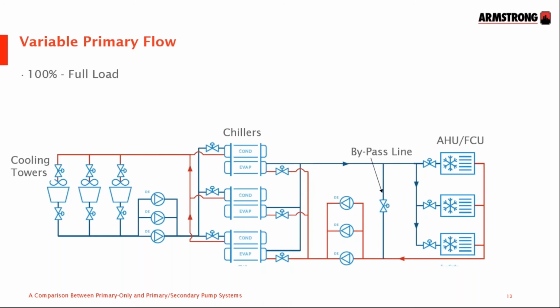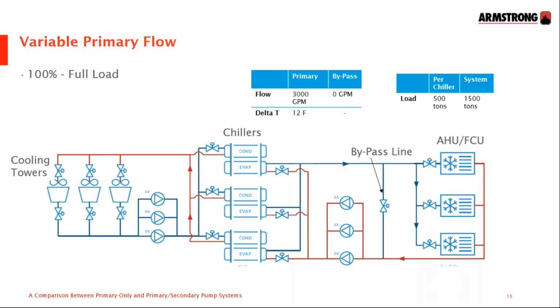So let's look at the full load picture for variable primary flow and put some numbers to our design, and we'll operate the system at varying loads. The design will have three 1,000 gallon a minute pumps. They're no longer sized for 100 foot or 150 or 50 feet. They're sized for 140 foot of head, which is less than the sum of the heads of the primary and the secondary.